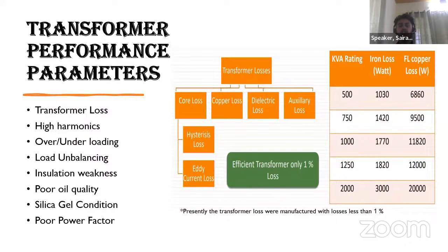Core loss is independent of the loading that we are providing to the transformer. The copper loss is related to the loading that we are providing to the transformer. Presently, transformers are manufactured with losses of less than 1%. Then higher harmonics have an effect. Loading, either overloading or underloading, also affects the performance of the transformer.